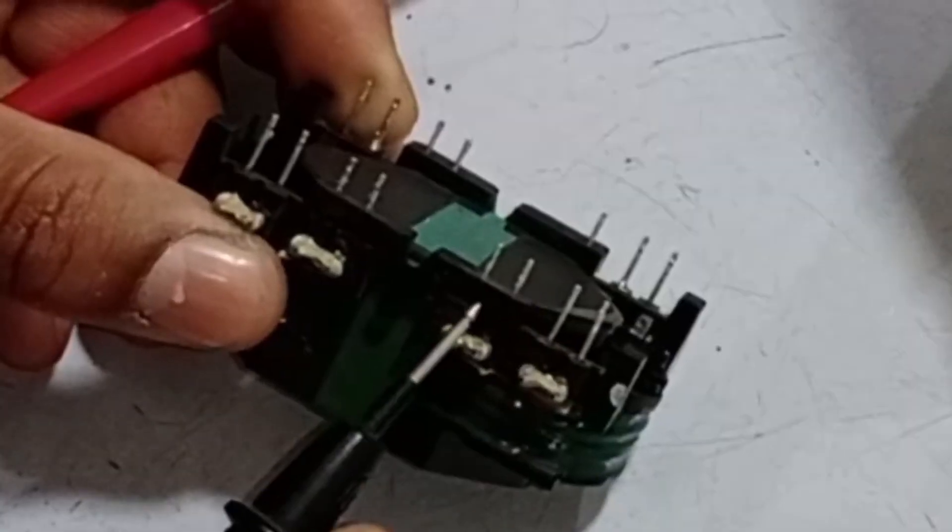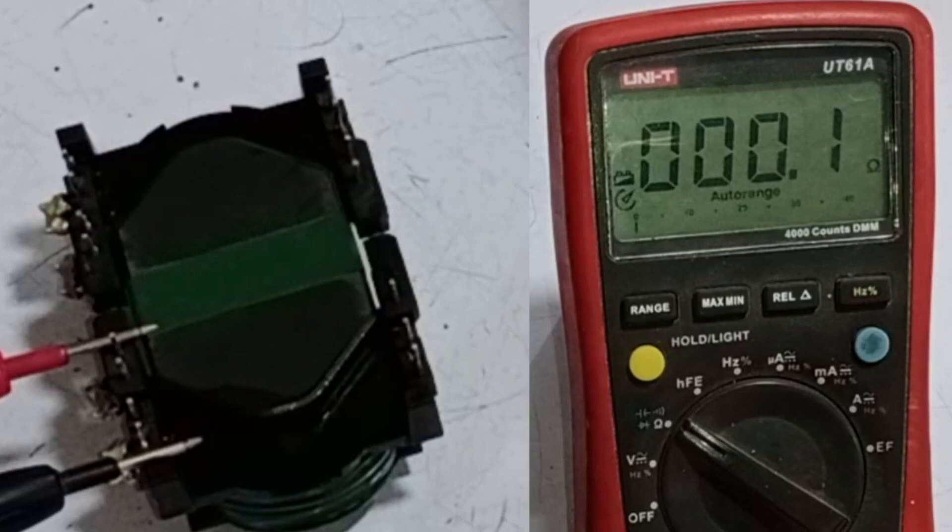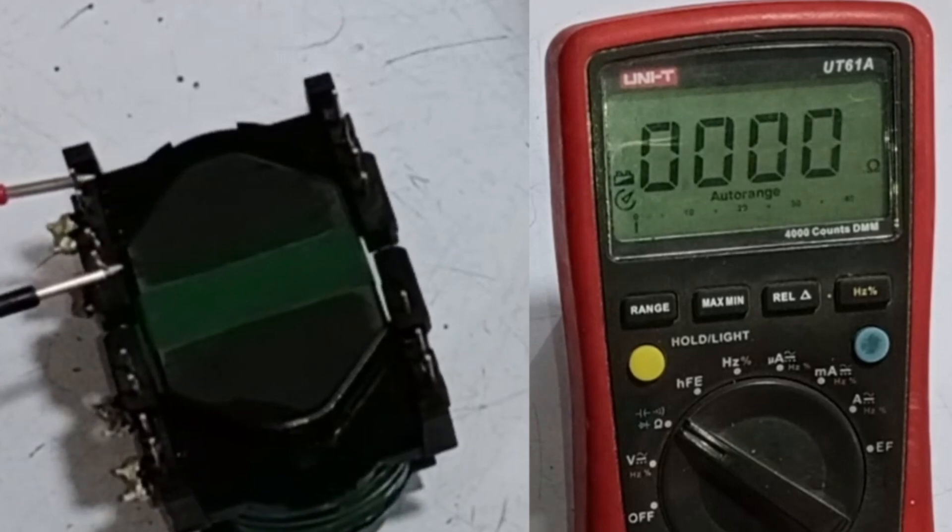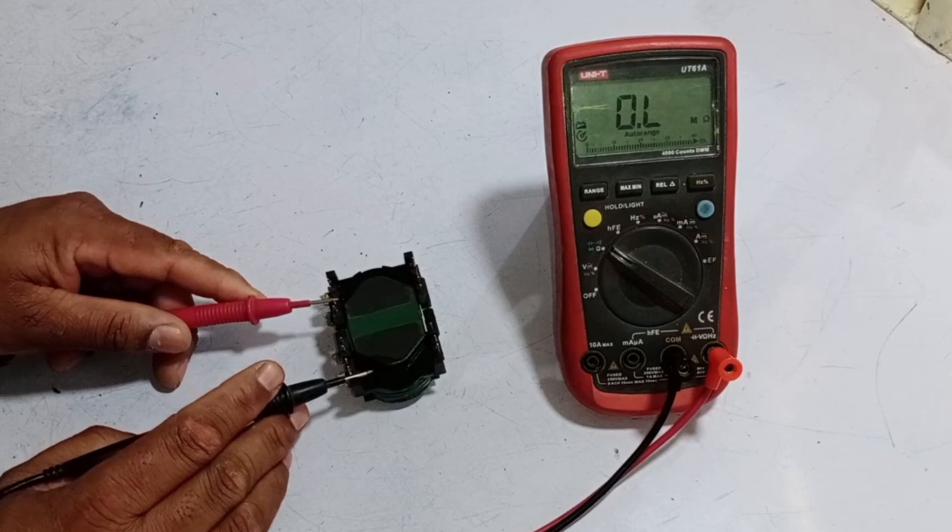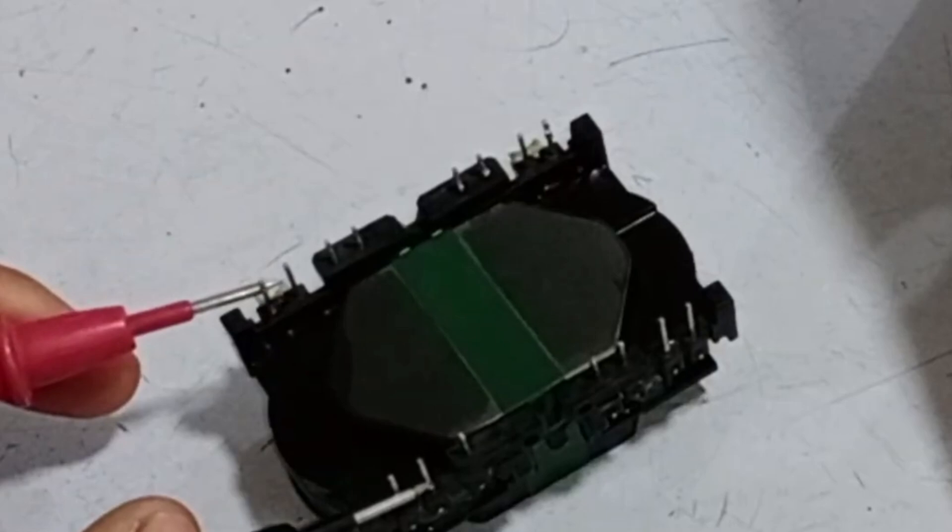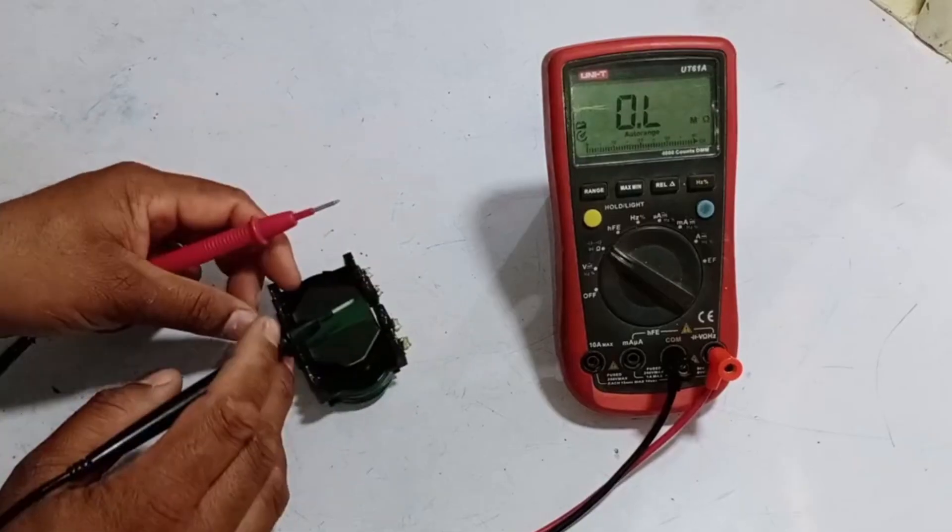First, we will check the points with the thick wires. These wires should have a small amount of resistance. As you can see, it shows a resistance of 0.2 ohms. Similarly, if we check the next point, it also has resistance in the same range. There should be no short circuit between these wires, and additionally, there should be no short circuit between these wires and the other wires. In other words, these are four separate coils, each working independently.